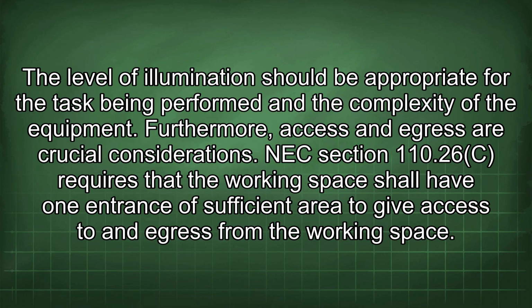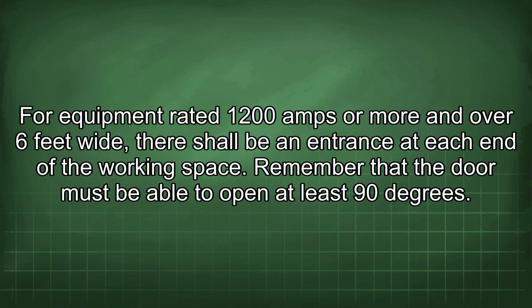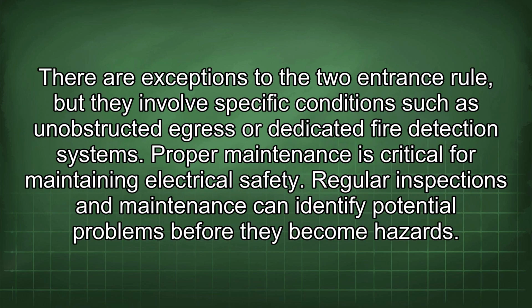NEC Section 110.26(C) requires that the working space shall have one entrance of sufficient area to give access to and egress from the working space. For equipment rated 1200 amps or more and over 6 feet wide, there shall be an entrance at each end of the working space. Remember that the door must be able to open at least 90 degrees. There are exceptions to the two-entrance rule, but they involve specific conditions such as unobstructed egress or dedicated fire detection systems.